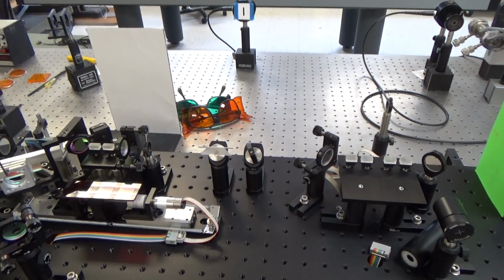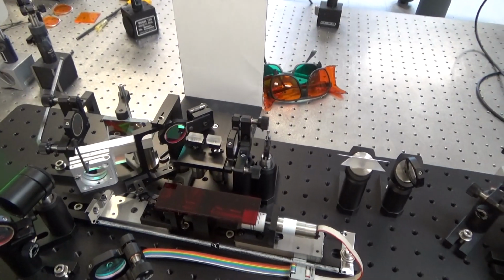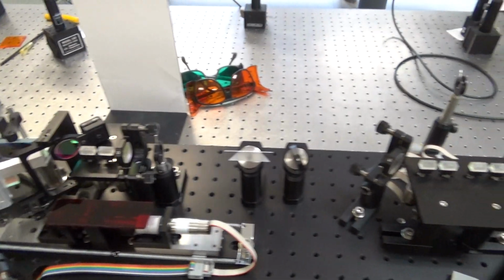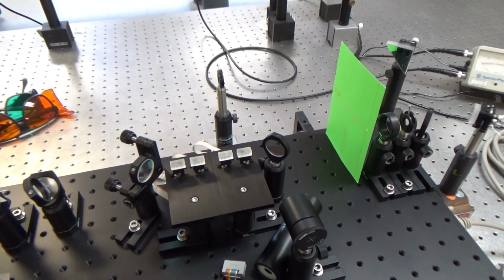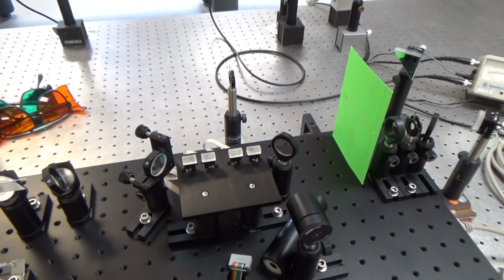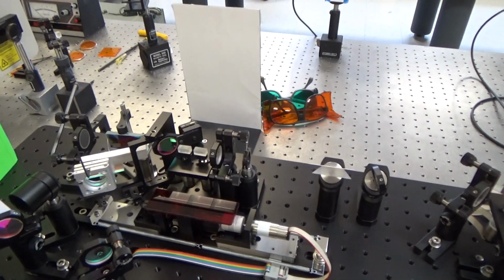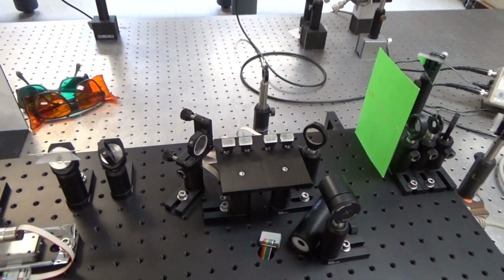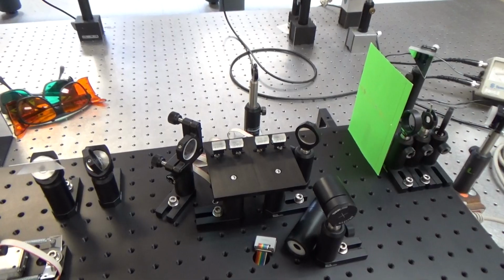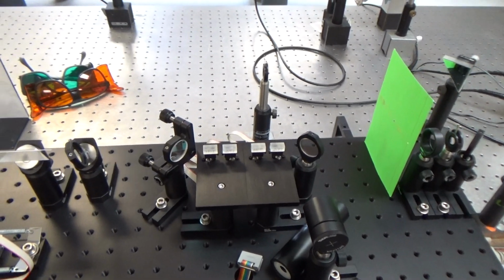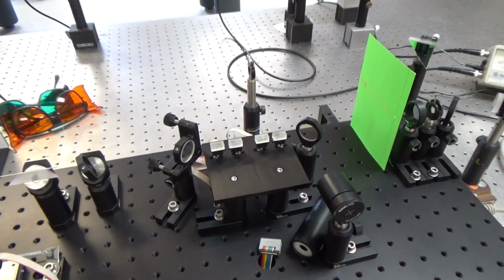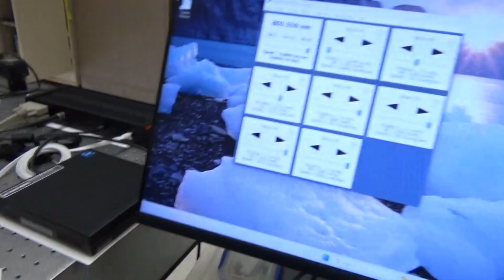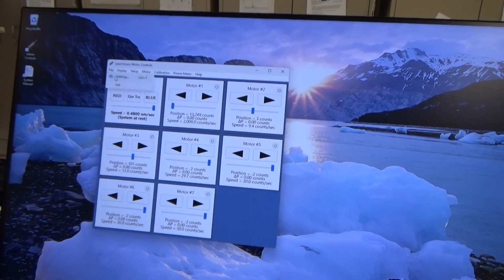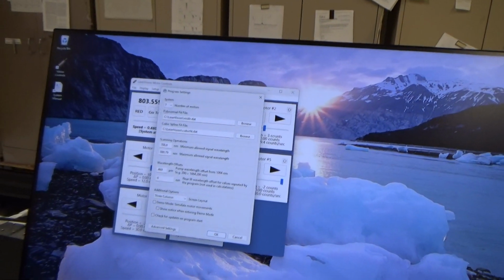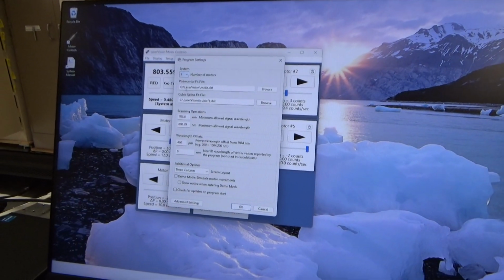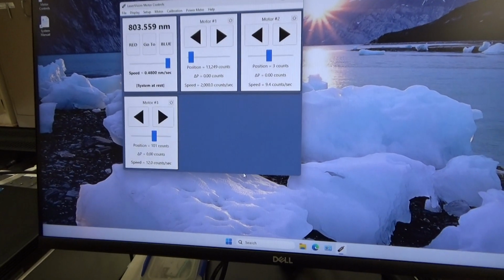At normal incidence, the oscillator stage is running at around 803.5 nanometers, and the amplifier stage is set at 745 nanometers. I'm going to first calibrate the OPO stage, so I'm going to deactivate the OPA motors, leaving them parked at 745 nanometers, so I can come back to that wavelength later and pick them up. You can do that just by going into the settings menu here and changing the number of motors in the system to 3. Okay.